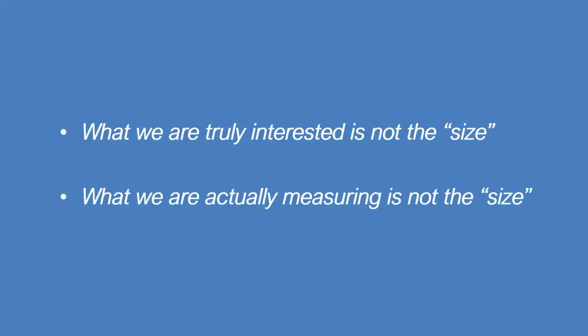And the second part is that what we are actually measuring is not the size. Hopefully, by the example of dynamic light scattering, we're measuring a time-dependent phenomenon. By laser diffraction, we're measuring angular-dependent light scattering. What we are measuring is the response of the particle with light, the interaction with the light. We are not measuring the size itself, but we are converting the signal obtained from the scattering to something relatable to the size. The same goes for AF4 fractionation, and also the imaging analysis for the subvisible particles. So in a way, what we are measuring may not be exactly the size.